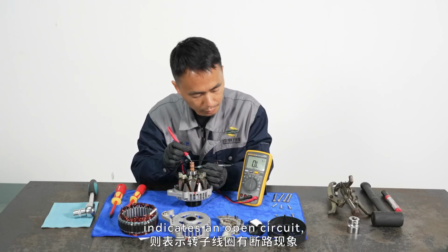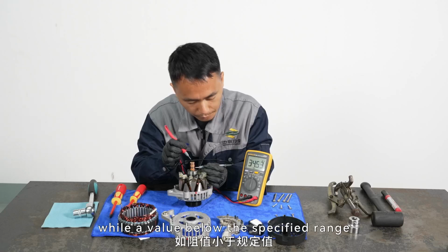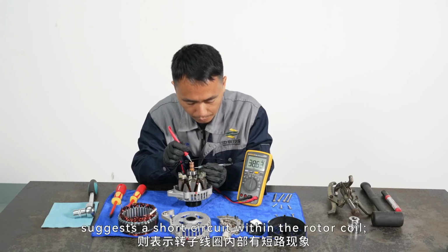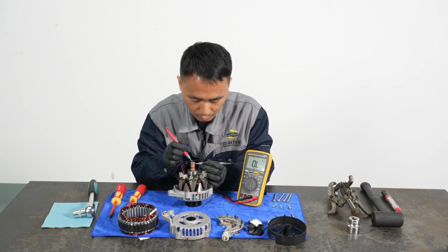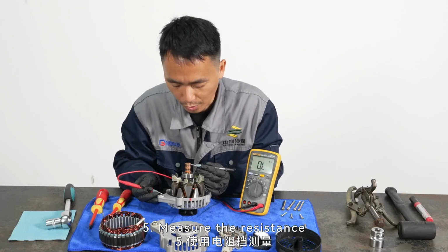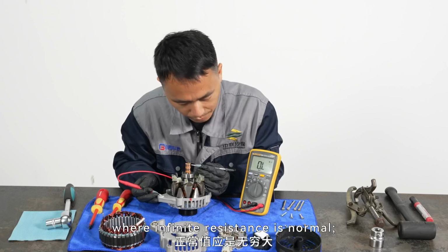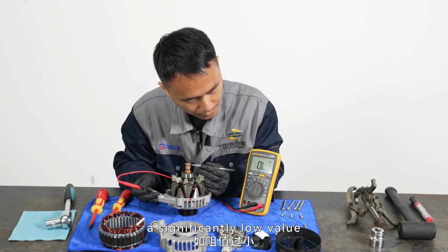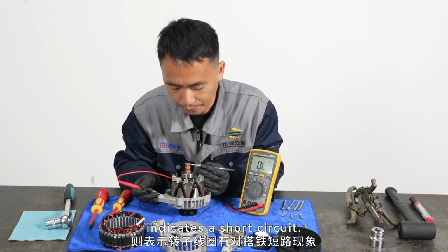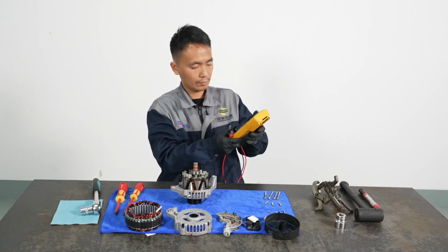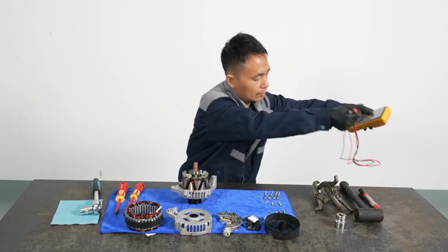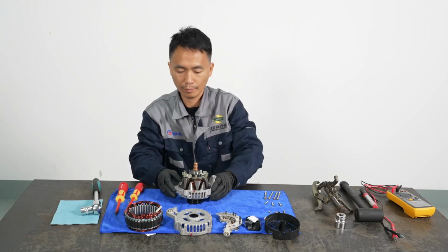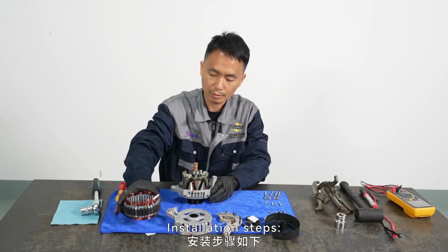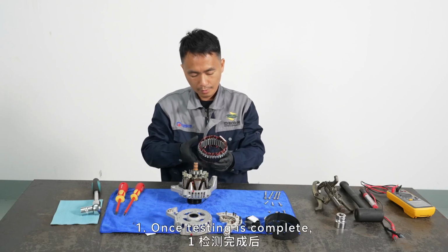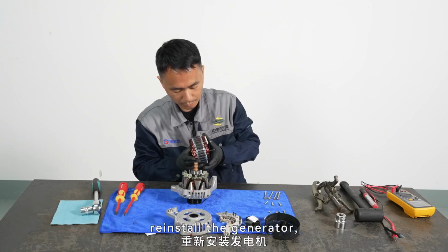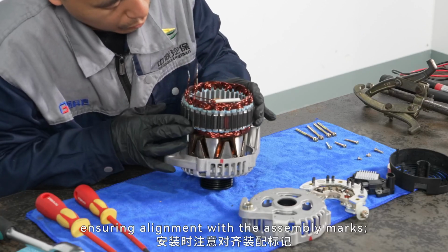Infinite resistance indicates an open circuit, while a value below the specified range suggests a short circuit within the rotor coil. 5. Measure the resistance between the rotor coil and the core. Where infinite resistance is normal, a significantly low value indicates a short circuit. Installation steps. 1. Once testing is complete, reinstall the generator, ensuring alignment with the assembly marks.